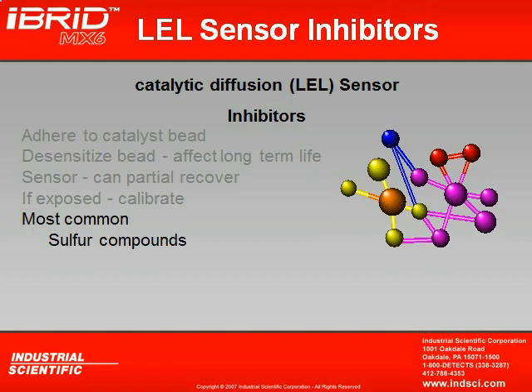Just to give you a little heads up, a test we did at Industrial Scientific is we took a batch of our combustible sensors and applied 1,000 ppm of hydrogen sulfide to them for 1 hour. As a result of the 1,000 ppm exposure for 1 hour, the sensors lost 16% of their life. Was the combustible sensor still good? Absolutely, but 16% of their life was lost as a result of 1,000 ppm H2S exposure for an hour.